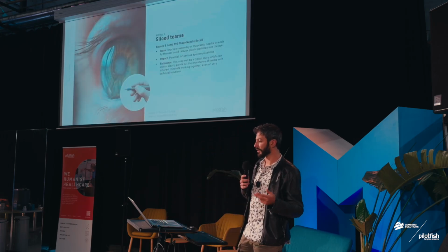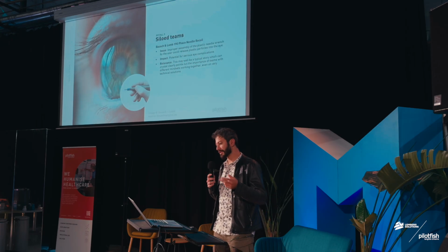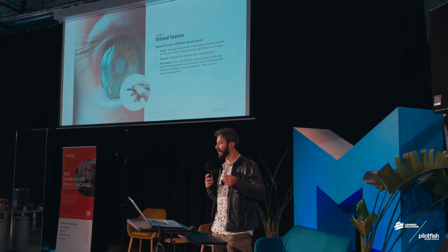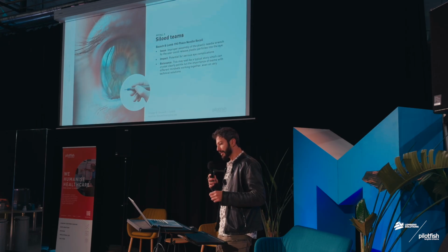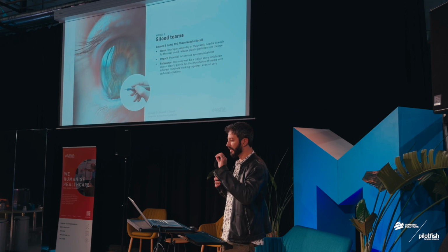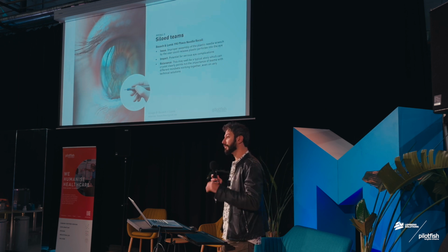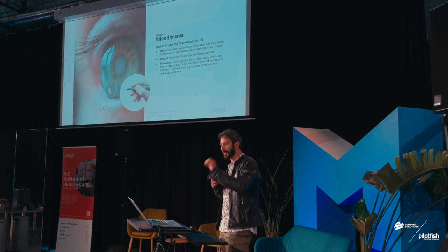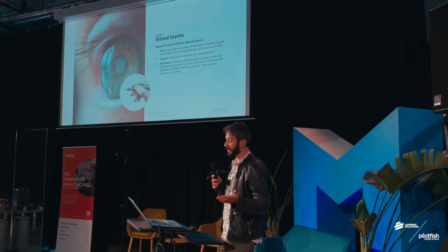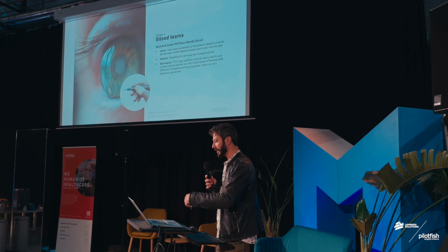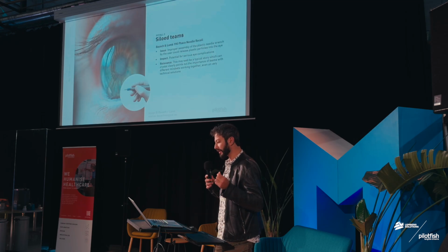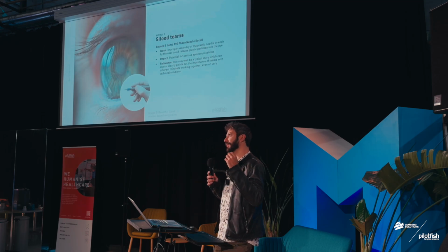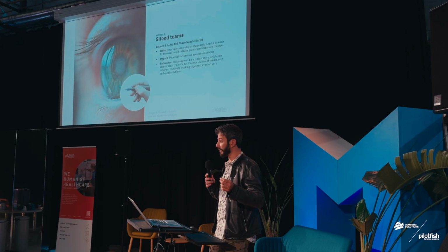Now this third product is eventually a needle that you use during cataract surgeries. Essentially this was recalled because if you improperly assemble it, plastic pieces will break off the wrench and they might end up in the patient's eyes, which is a situation that is kind of multidisciplinary.